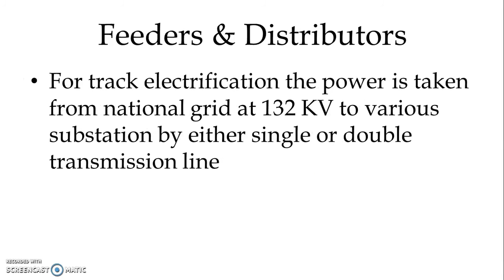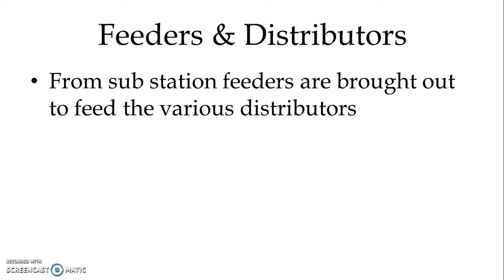Now let us start with feeders and distributors. For track electrification, the power is taken from the national grid normally at 132 kV to various substations by either single or double transmission line. From the substation, feeders are brought out to feed the various distributors.